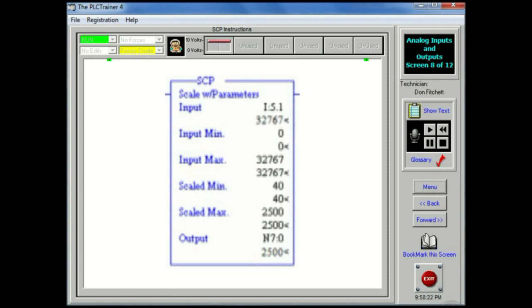The parameters needed by the SCP instruction are: Input - the value to be scaled, which may be a word address or an address of floating point data elements. Input Min - the minimum value for the input, low end of range. Input Max - the maximum value for the input, high end of range. Scaled Min - the minimum scaling value representing the low end of the scaled range of the input. The scaling relationship is linear. Scaled Max - the maximum scaling value.